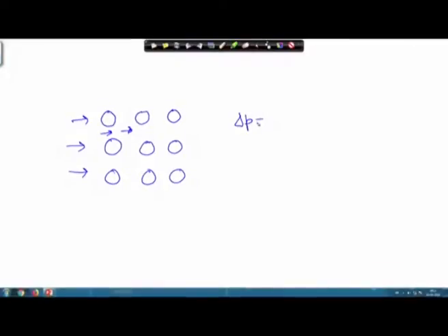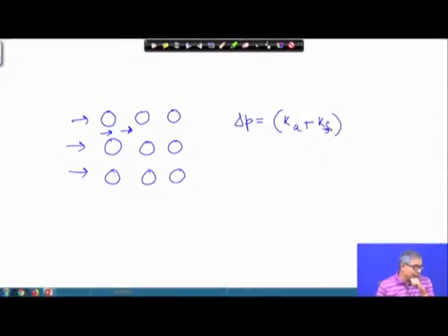All these things generally are done in some sort of a correlation form, and one can write delta P, the pressure drop, is equal to, due to two components, K acceleration plus K friction, times half into rho V max square. So, this simple formula is used. All the complexity of the pressure drop has been taken care of by this simple formula.